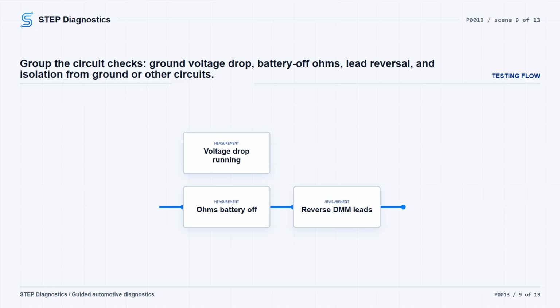When checking resistance or continuity, reverse the leads and compare the readings. If the resistance changes when the leads are swapped, the result is not valid unless the circuit contains a semiconductor.